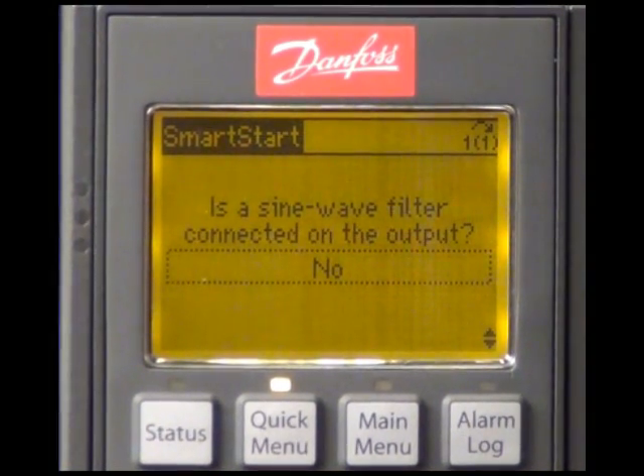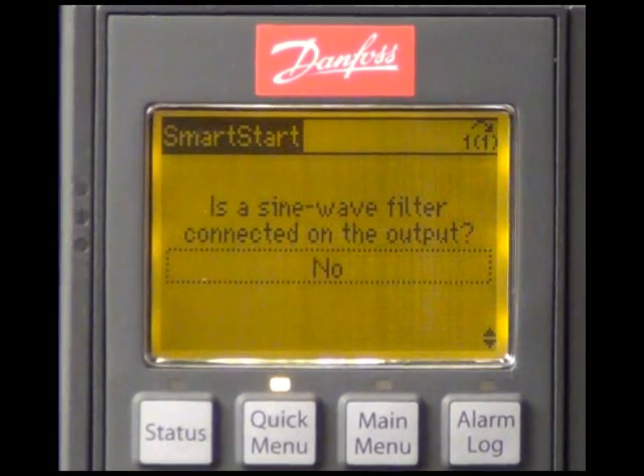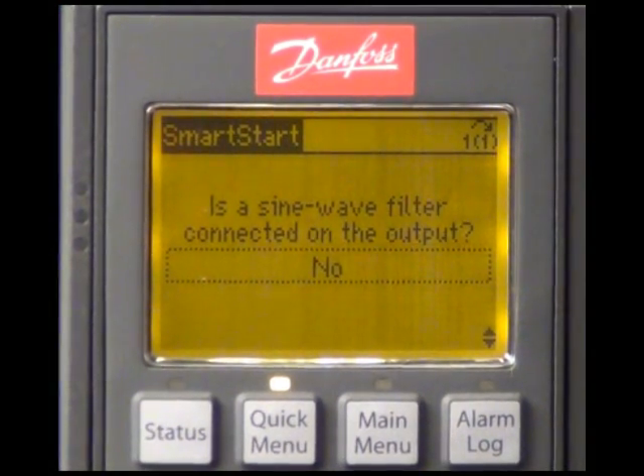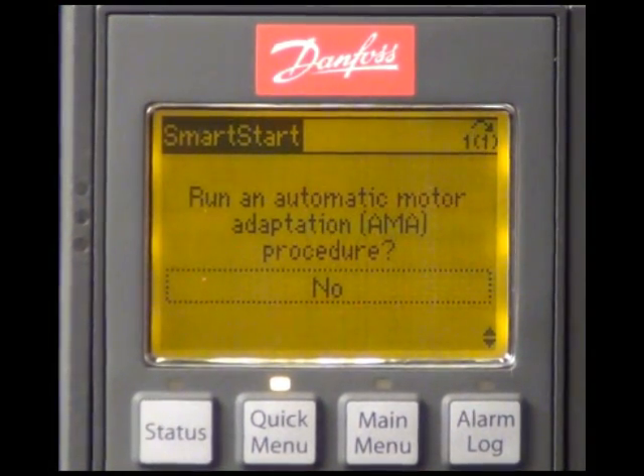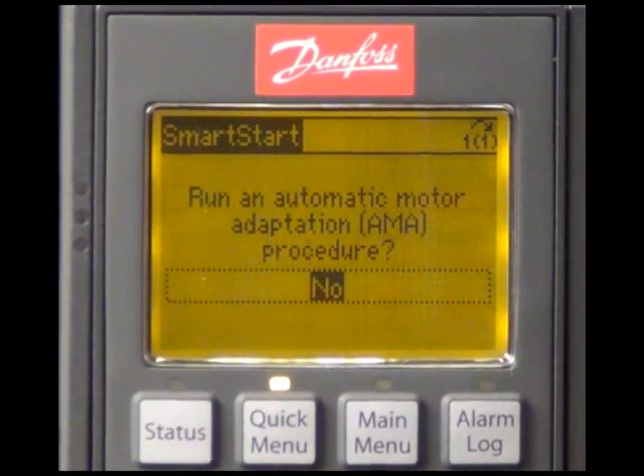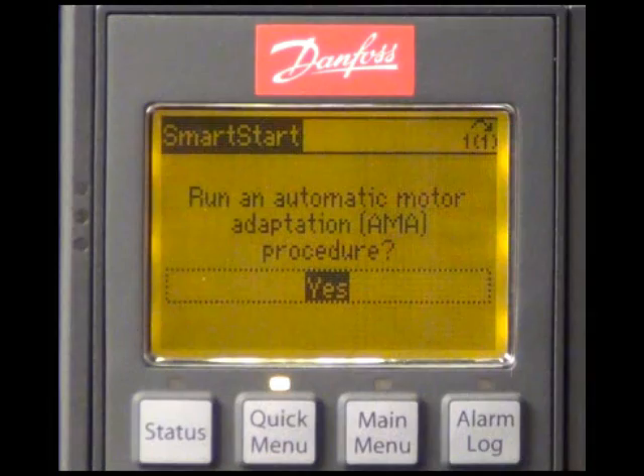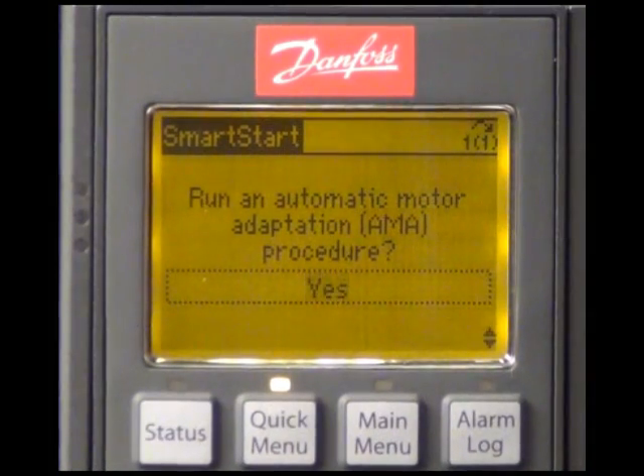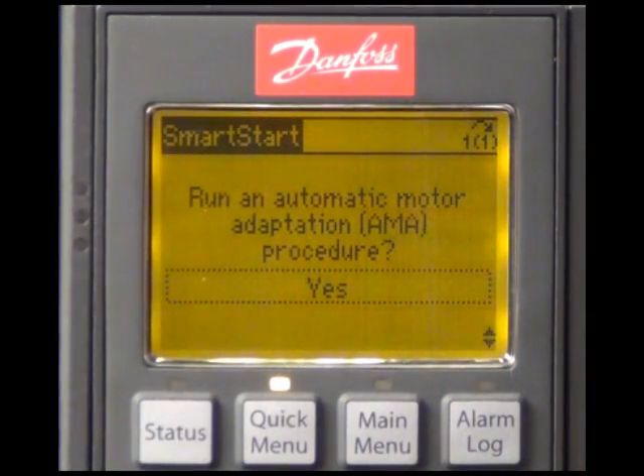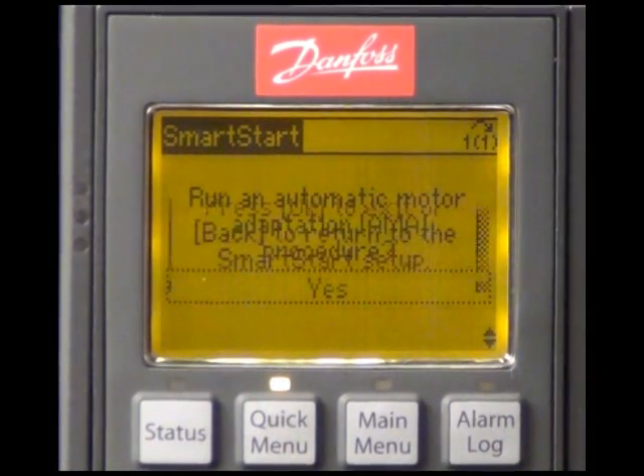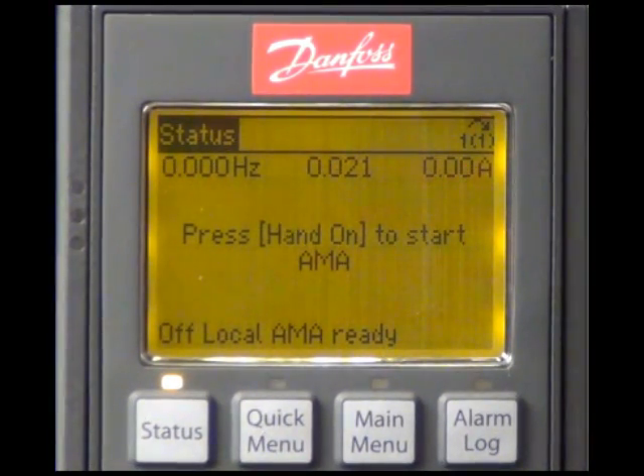We are not using a sine wave filter at the output of our drive. We will now start the automatic motor adaption AMA and confirm this by pressing hand on.